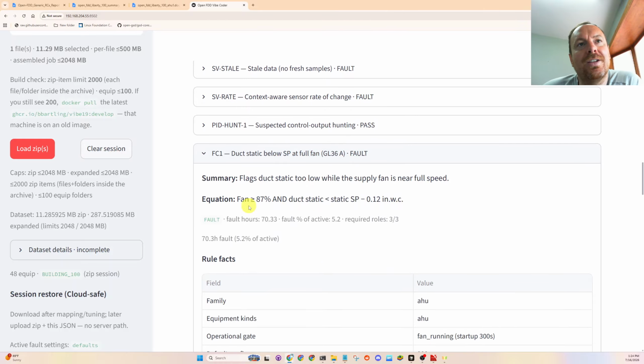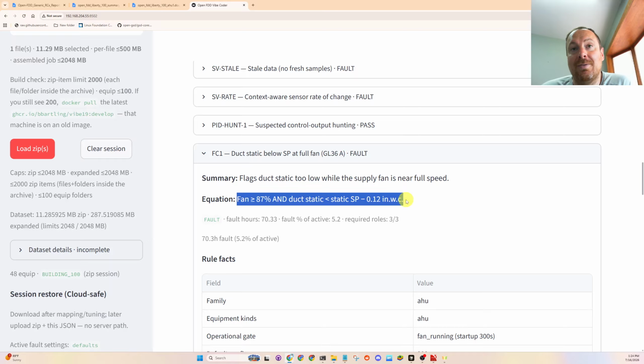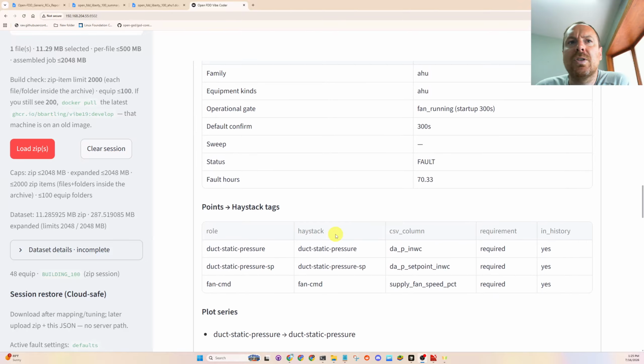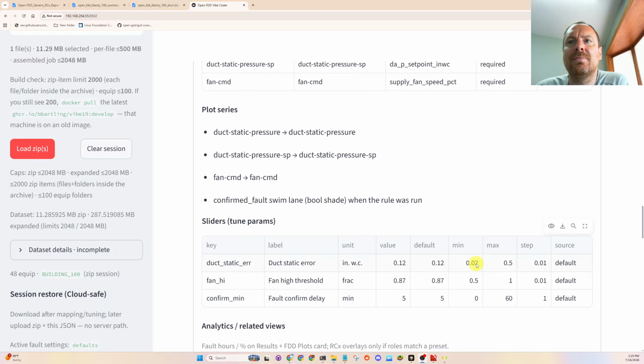And this is a good one too, because these fans are monsters, really big fans. When those fans go up to 100%, there's a lot of power being pushed through them. And with the fan laws, it's a cubic relationship too. So if you can trim back fan speed just the teeniest bit, it has a cubic relationship for electrical power consumption. So we do have some faults here.